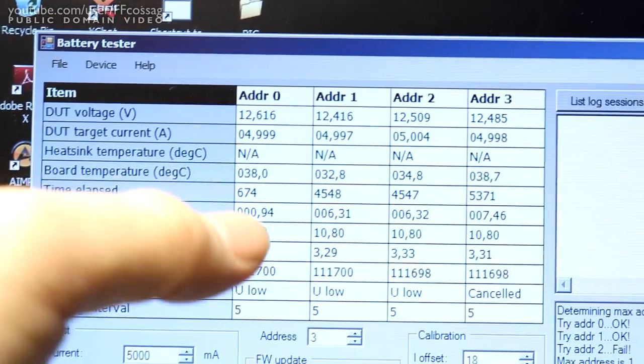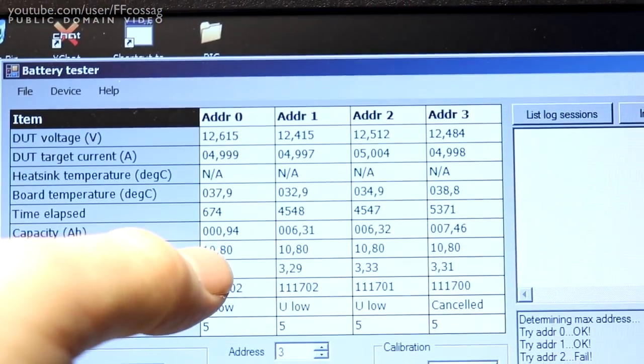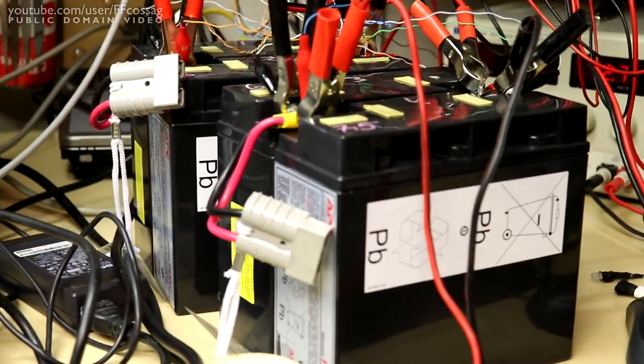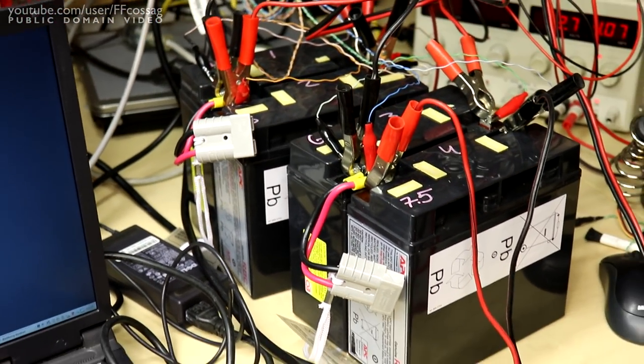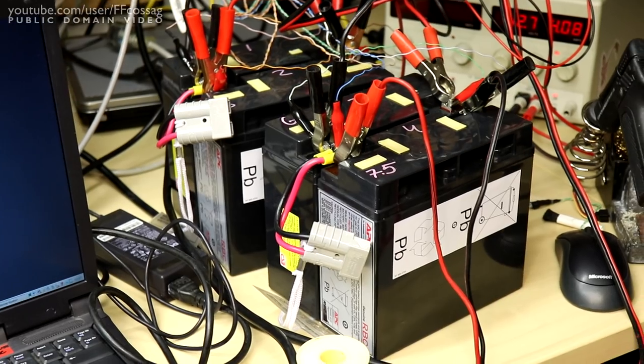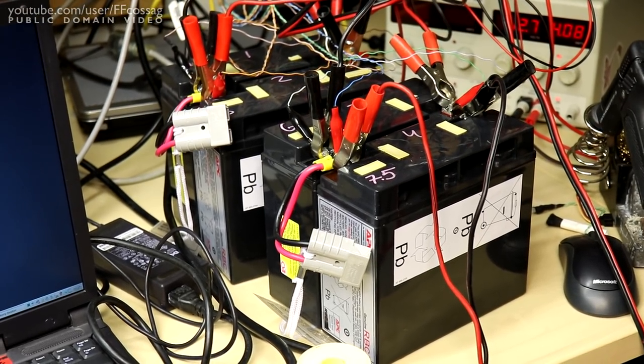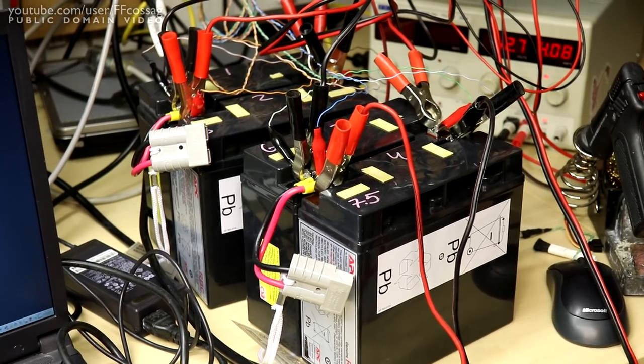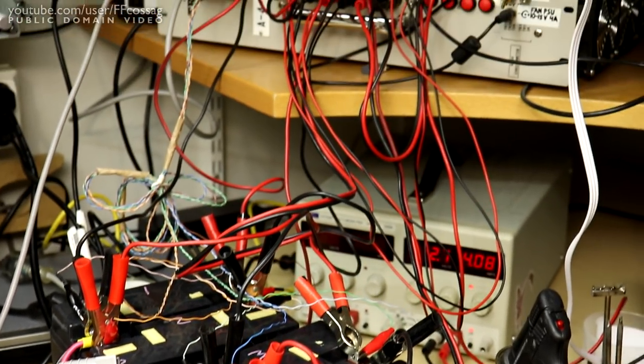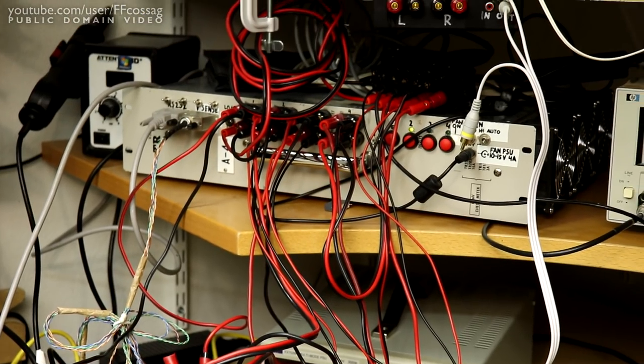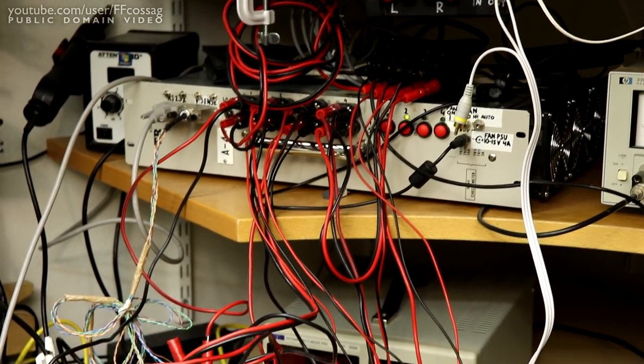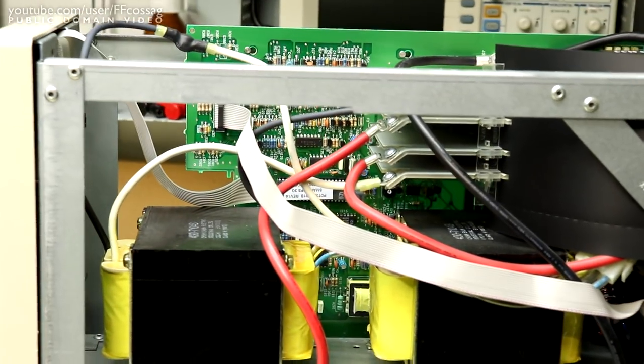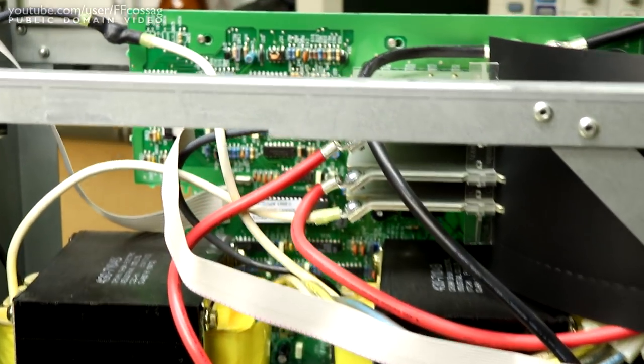And the testing is done and I don't want to say I told you so, but come on. Six amp hours, just as predicted, save for the first battery which is at one amp hour. It's an outlier, it's terrible, and that thing's been the thing that's been wrecking this UPS's utility because a one amp hour battery is not going to provide very well when you're dealing with a 3000 watt unit. So these batteries are garbage. I'm going to let them charge then put them aside.